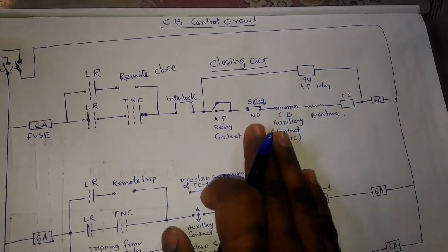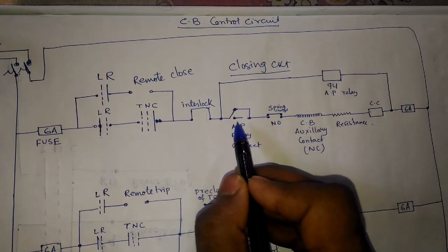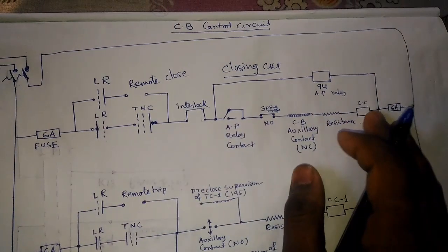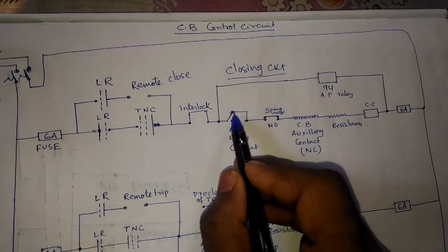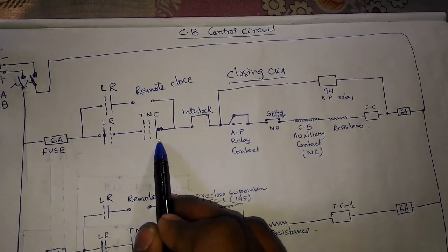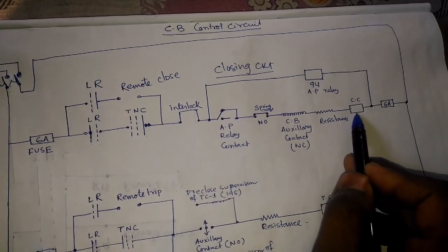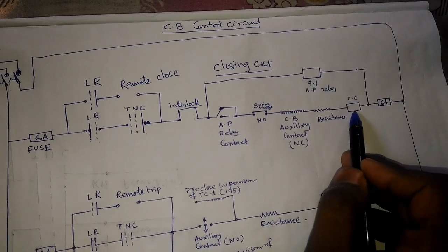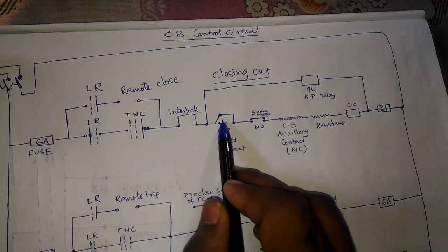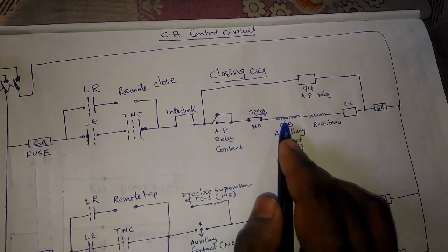After the closing command is executed and the circuit breaker is properly closed, the anti-pumping relay NC contact will change to NO contact. This path is cut by this NO contact. So if the LR switch or TNC switch is malfunctioning, the circuit breaker will not receive the closing command repeatedly. The closing coil and circuit breaker will be safe. By the anti-pumping relay, we cut this NC contact to NO contact and this path becomes inactive.